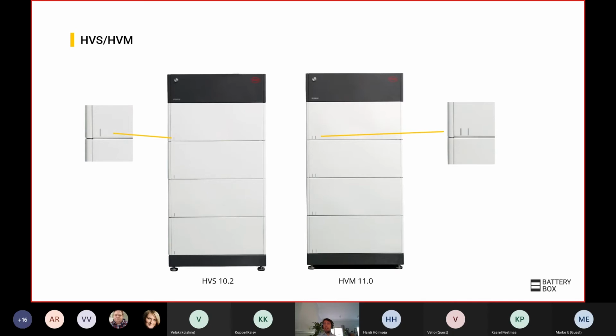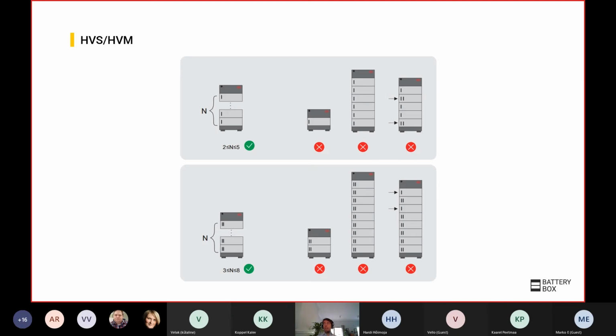When you do this, just in general, we have never seen this issue in the field up to now. But just in case you have doubts and you have several modules in your warehouse, some HVS, some HVM, you can differentiate them because they have one bar for the HVS and two bars for the HVM, and they cannot be combined together. Remember, the HVS can have 2 to 5 modules in one tower. The HVM can be 3 to 8 modules in one tower.